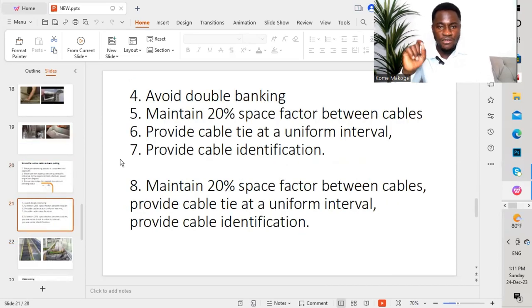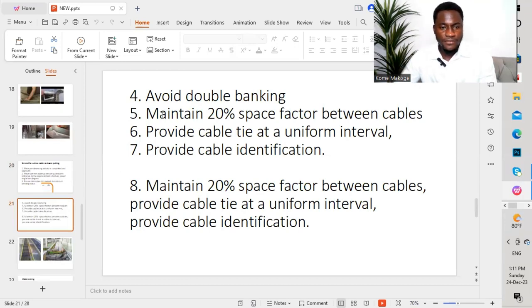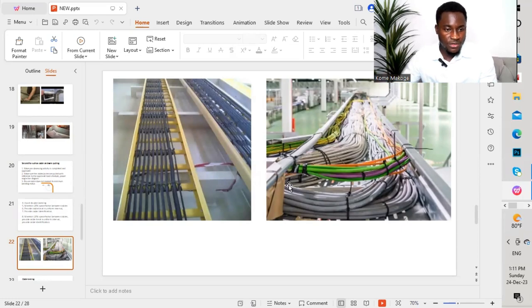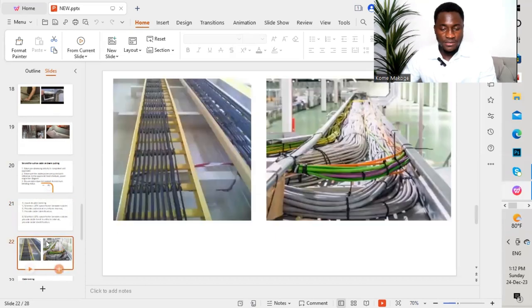The fourth point: avoid double banking — avoid cables running across each other. The fifth point: maintain a 20% space factor between cables. As shown in the graphic, when they pull cables, they maintain a 20% space factor. Avoid crossing cables over on top of another cable. Also, provide cable ties at a uniform interval — as shown in the graphic, cable ties have been provided after cables have been pulled on the cable ladder.